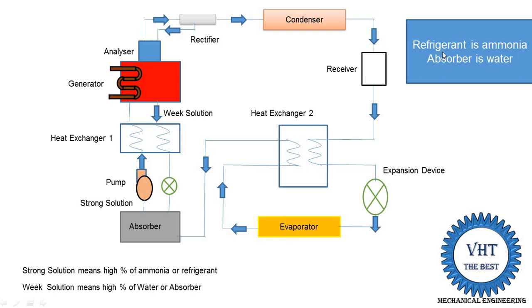In this system, ammonia is used as the refrigerant and water is used as the absorber. Ammonia is circulated in the right-side part of the system — that is, the condenser, receiver, expansion device, and evaporator. In the left-side components — absorber, heat exchanger 1, analyzer, and generator — a mixture of solution is circulated. The right-side portion contains only the refrigerant ammonia, so in the condenser only vapor refrigerant is supplied. The vapor refrigerant rejects heat in the condenser and is converted into liquid ammonia, then supplied to the receiver.